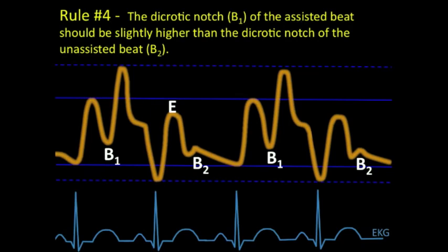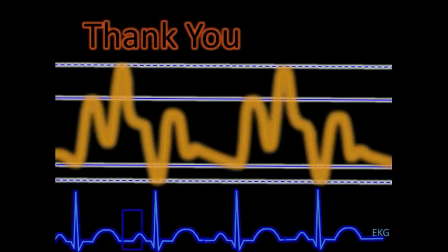So the curve in our example meets all 4 of those criteria. And indeed, in this patient, the balloon pump was positioned properly, and essentially our balloon was optimized. So I think in our next video, we'll go into some of the things that go wrong with the balloon pump. But for the purposes of this video, I just wanted to give you a brief introduction to intra-aortic balloon pumps and the aortic pressure curve that goes along with them.